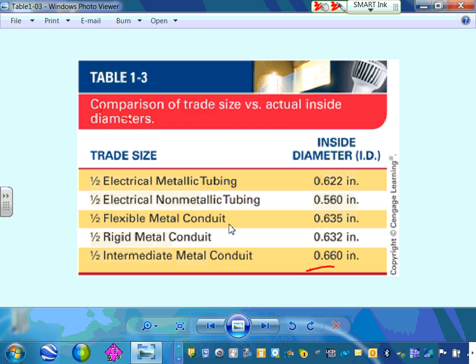Here's an EMT conduit. All of these are half an inch EMT and non-metallic tubing, but look at the actual interior diameter — they're different. They're all called half an inch in the trade: rigid, EMT, PVC. These are different types of approved conduits you'll be using. This one is 3/4 of an inch, but rigid, EMT, PVC, and non-metallic 3/4 inch all differ. There are close to 60 wiring methods in the code.